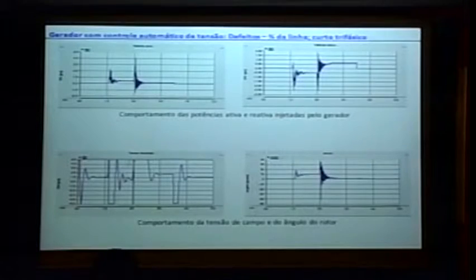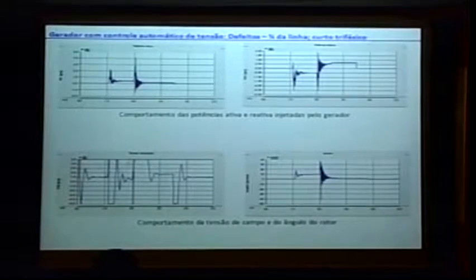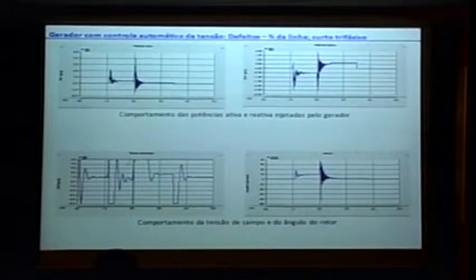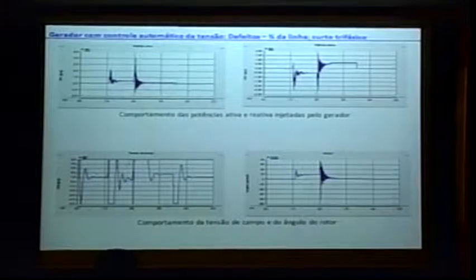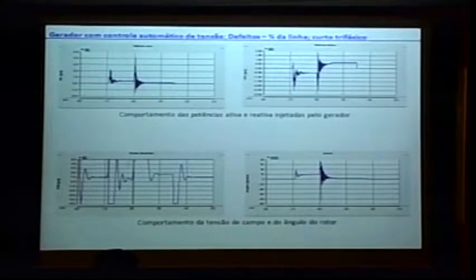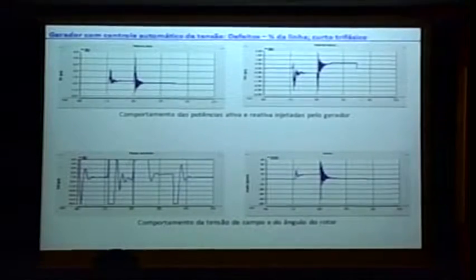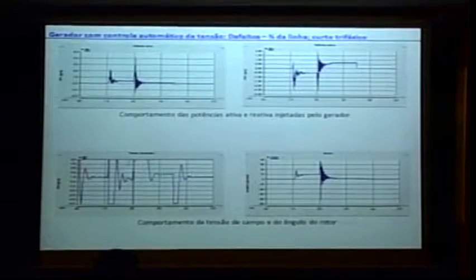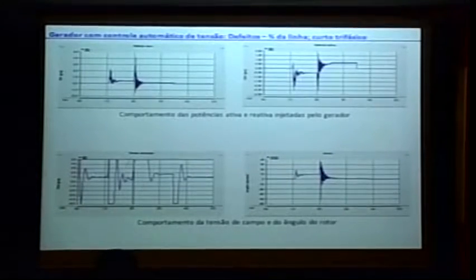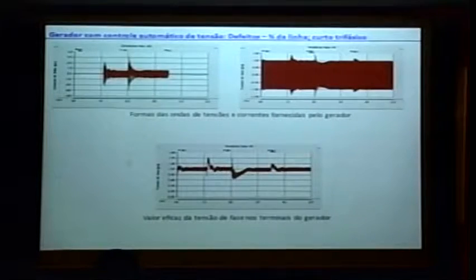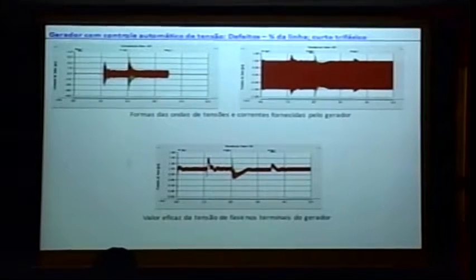After the short circuit is eliminated, it increases the field current to almost 2. Maximum value is 5 at the transient system. And after the elimination of the fault, it adjusts the voltage of the generator, bringing it close to 1 pu. Here's the load angle, because it fell because part of the line was disconnected. So the line was shortened. Here's the voltage profile on the generator. We had a voltage.